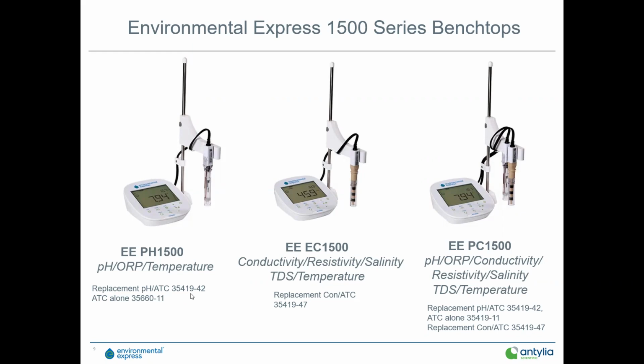Now, what comes standard with the 1500 is an all-in-one, as I call it. It's got the pH combination electrode as well as a temperature element inside, so it'll measure pH and temperature. Conductivity is the same. It has the conductive plates as well as a temperature element built in. And then obviously the PC model uses one of each of those electrodes.